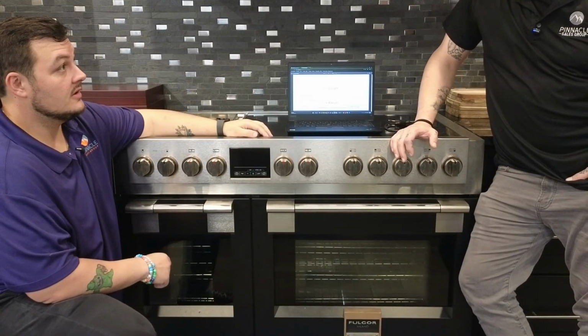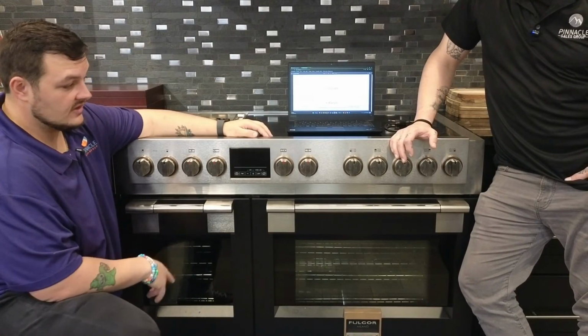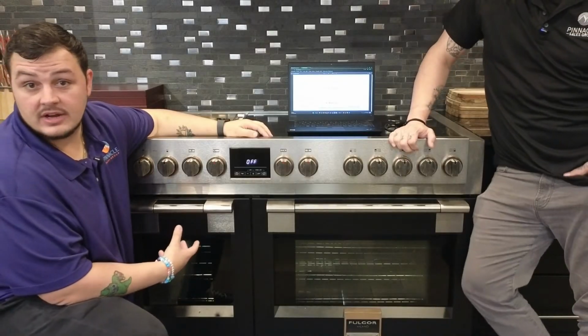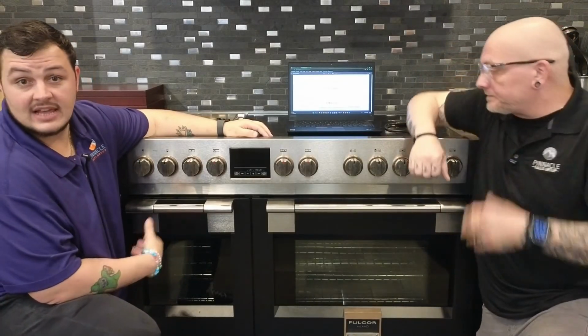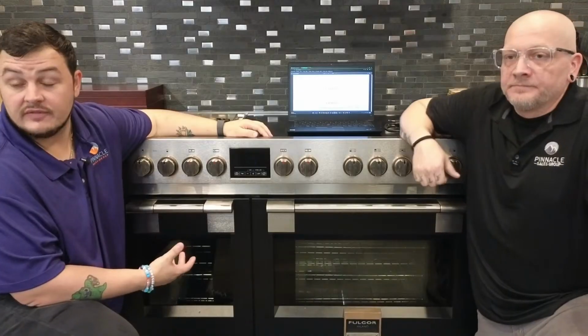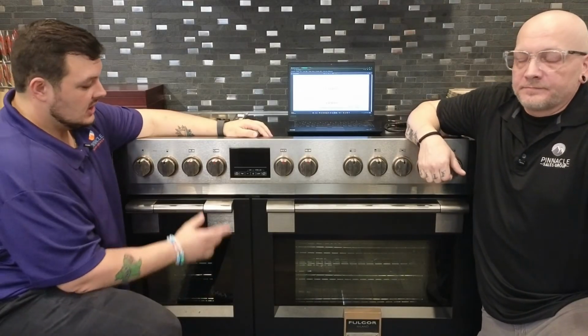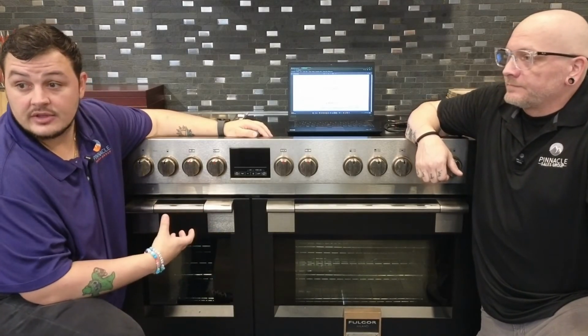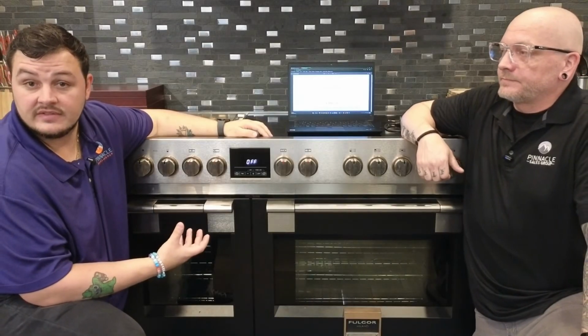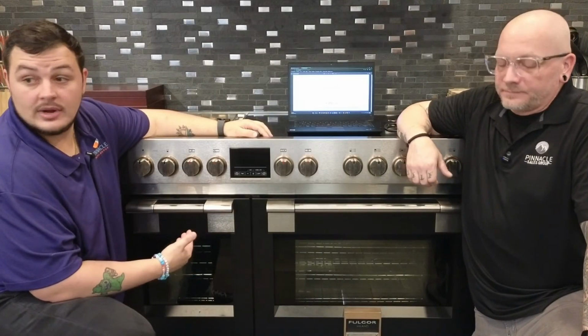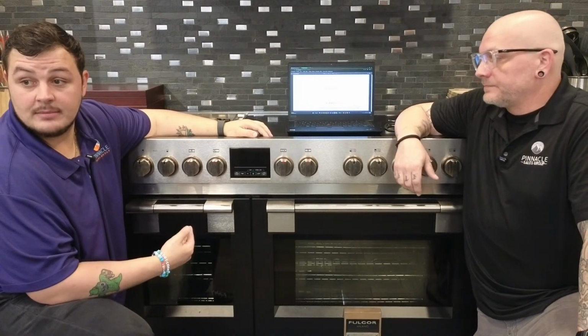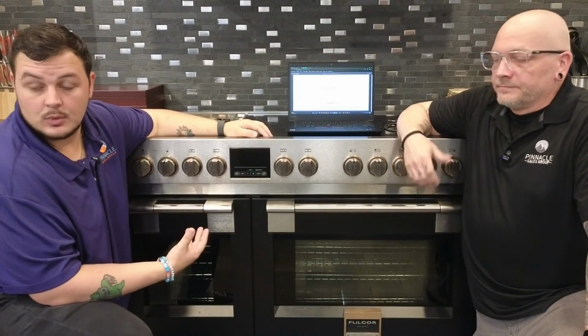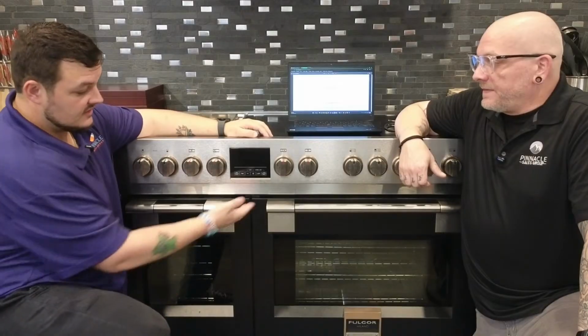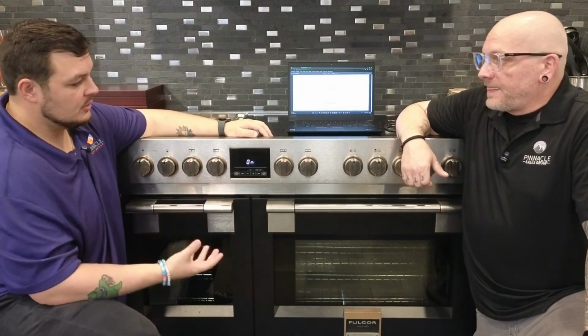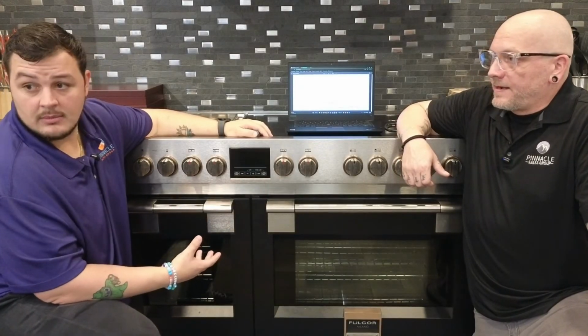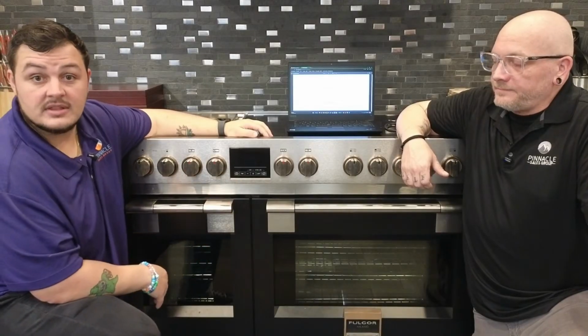My favorite is the temp probe test. If a homeowner says the oven isn't heating properly, isn't cooking food, or they're burning food, you can get into the temp probe and check the real temperature. Preheat to 350, let it chime, go into service mode quickly, go to the temp probe option and check what it's at. We trust this temp probe in the unit more than an analog thermometer, so using this is the best option.